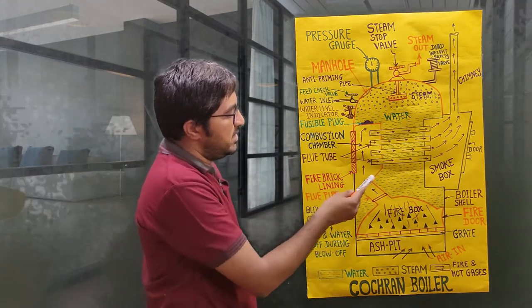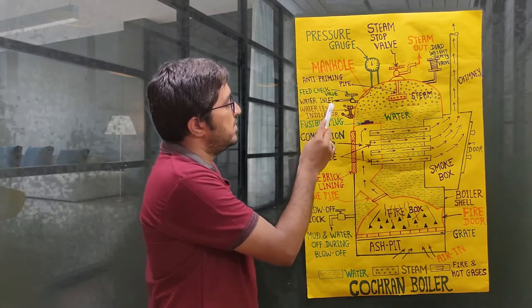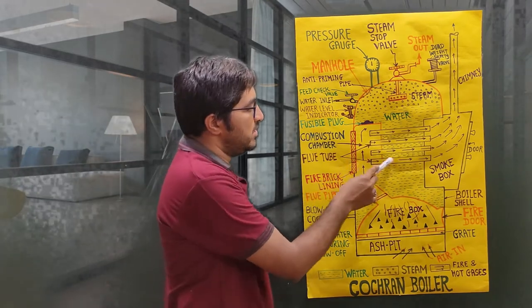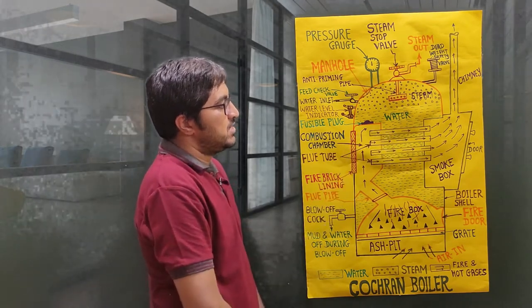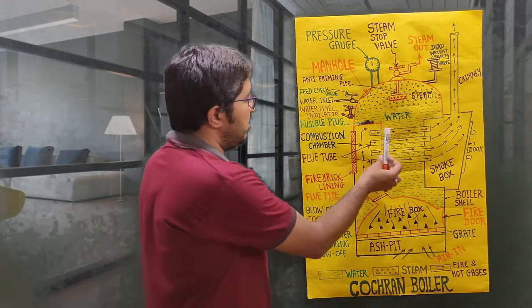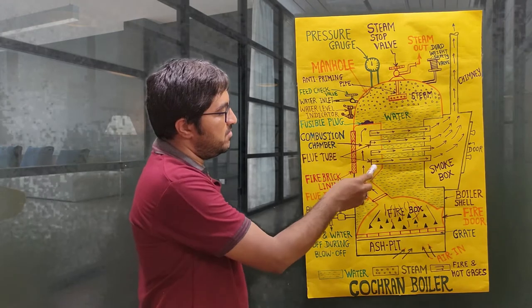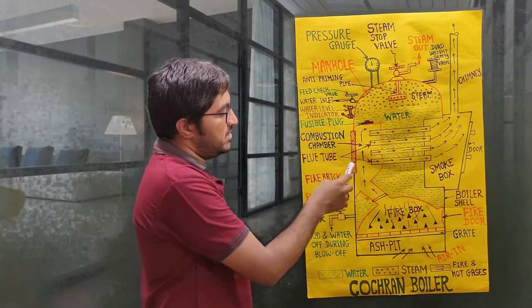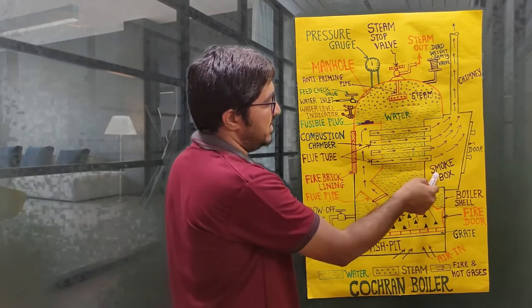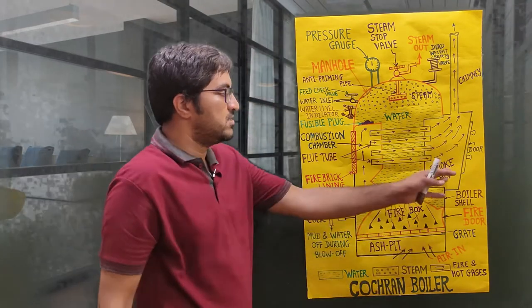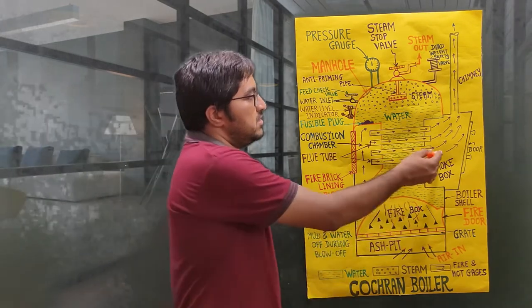Surrounding the tubes, water is filled through the feed check valve. The flue gases pass through the tubes and transfer heat to the water, causing it to boil. One side of the combustion chamber is connected to the fire bricks and tube openings, and the other side has a smoke box. The function of the smoke box is to collect the hot exhaust gases and then release them to the atmosphere through the chimney.